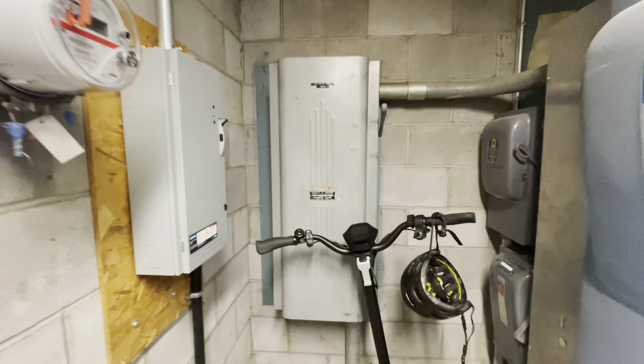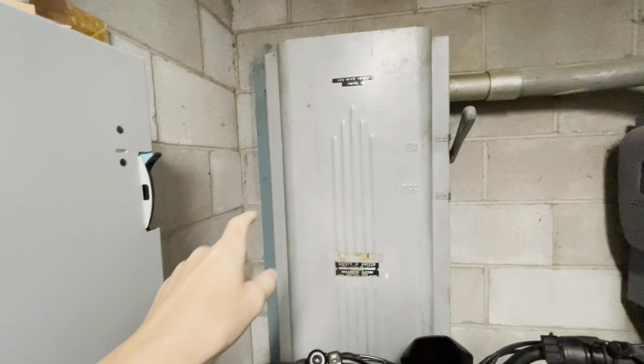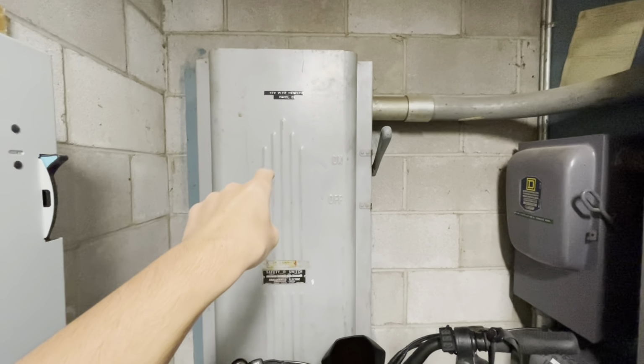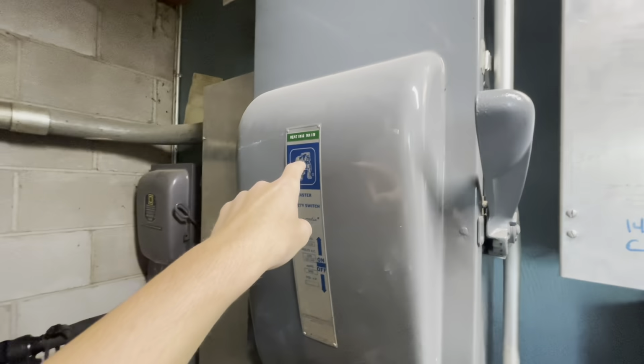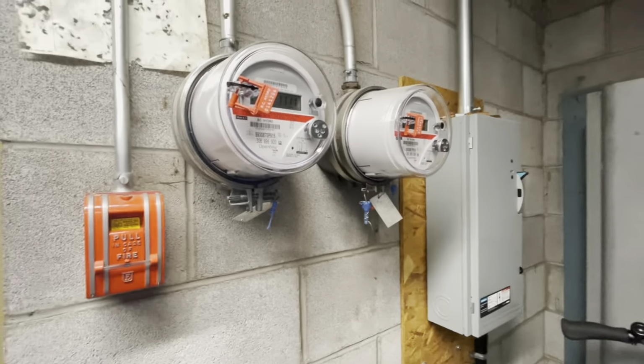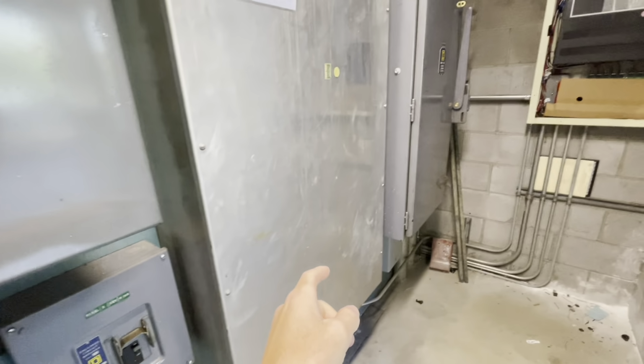The school's got so many disconnects in this electrical room. There's this one, not sure what it's for. New wing, heating panel. New wing is not by any means new. Then we've got heating main, lighting main, and the actual main. And two meters with where the CTs go somewhere. The donuts are probably in. Which one's sealed up?